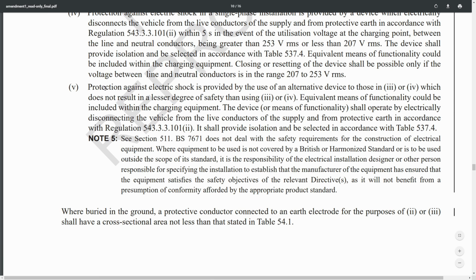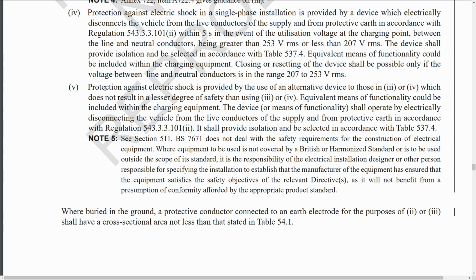So previously there were certain manufacturers of these charging points which have devices which claim to cover what's basically written in here. Previously, when you were actually using those, you couldn't fill in on the certificate that it complies with BS 7671 because, of course, it wasn't actually listed here. So you had to put that in as a departure from the regulations, and then you would put in the section on departures, we're using such and such a device from whoever the manufacturer is, and they have stated that this provides this particular feature, safety, and so on. The difference now is you can say, yes, it does comply with BS 7671 because of this particular item 5 here, and therefore it's sort of a minor technical change there.